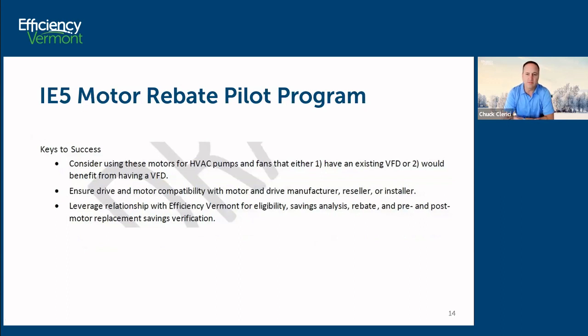Some keys to success for you as contractors. Consider using these motors for pumps and fans that either have a VFD or would benefit from a VFD. So we're purposely launching these 2 programs together. We're promoting you going into customer facilities and documenting VFD opportunities. But if you realize the motor is inefficient, it's old, maybe it's got some mileage on it, there is an option to order an integrated drive motor combination from the likes of ABB Baldor and others to come. So it could be an upgrade of both the motor and the drive, which gives the customer 2 points of energy efficiency improvement.